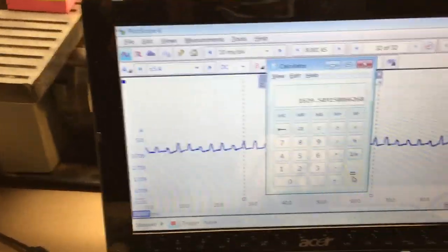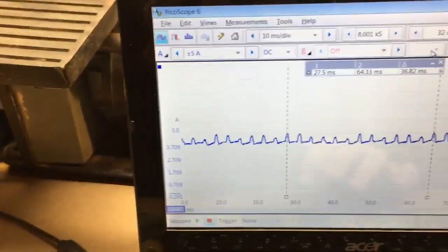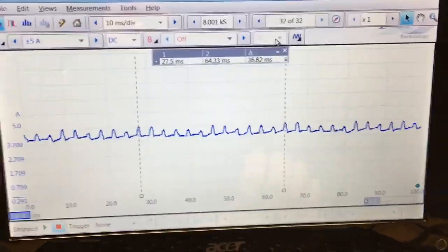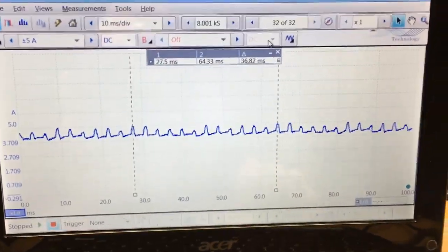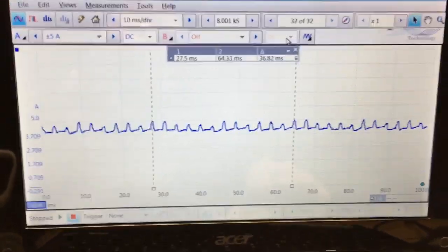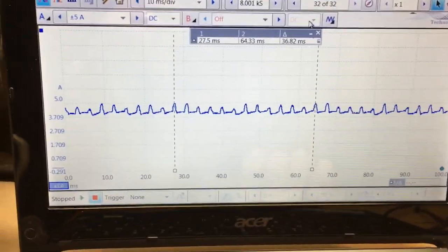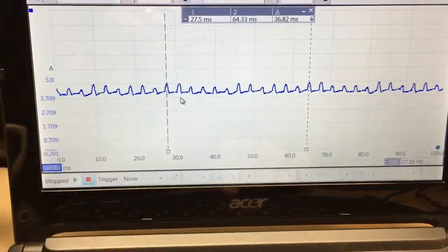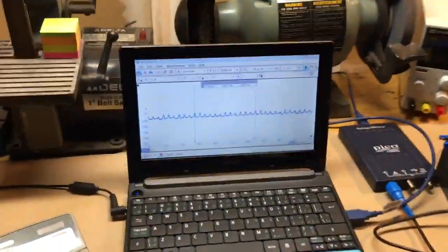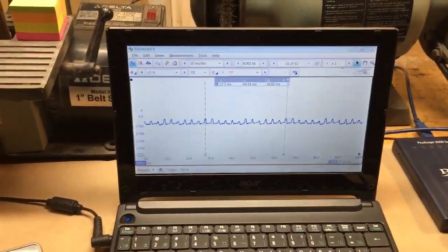I'm going to do a little series on current clamp waveforms and interpretation of them, what they actually mean. Because of course we can have different scenarios where we can have issues with the bushings or bearings in a motor assembly, issues with the windings, open or shorted, and a few other scenarios where, if you are familiar with how to interpret the waveform, it can tell you a great deal about the condition of the machinery that you're dealing with. Yeah, so that's enough for one night, I guess. Boys, hopefully you got some value out of that.